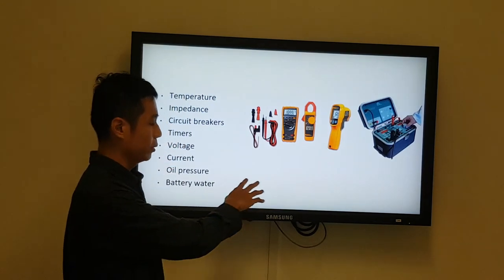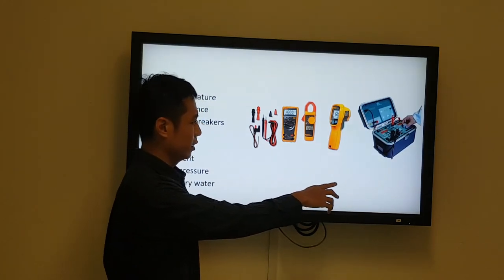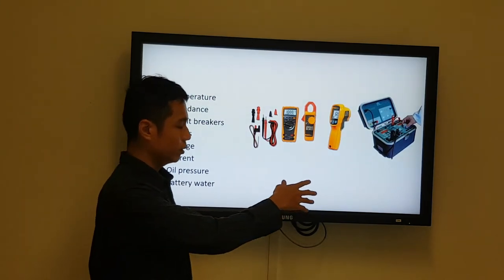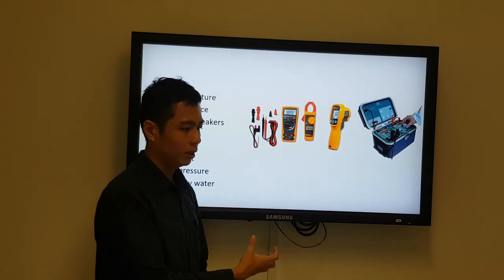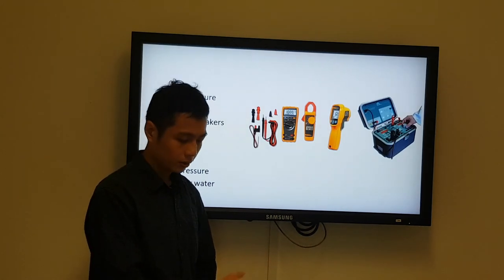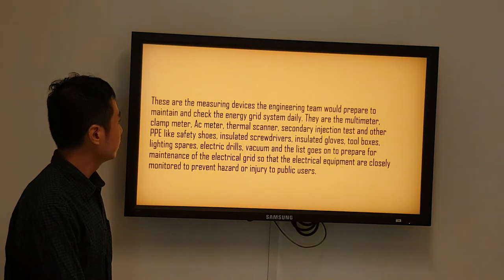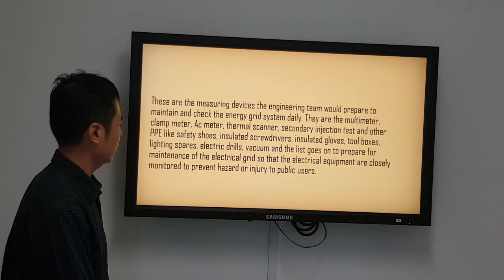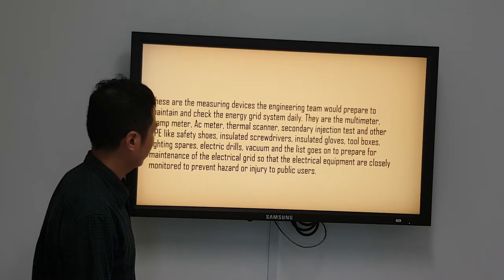The equipment the engineering team brings includes power meters, clamp meters, thermal scanners, and secondary injection testing boxes — to find out whether the circuit breaker or timer can withstand the fault current and handle overcurrent protection when the circuit breaker operates. These measuring devices — multimeters, clamp meters, and secondary injection test sets — are what the engineering team uses to maintain and check the energy grid system.